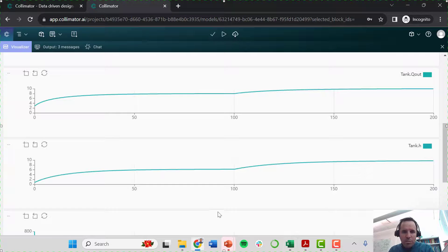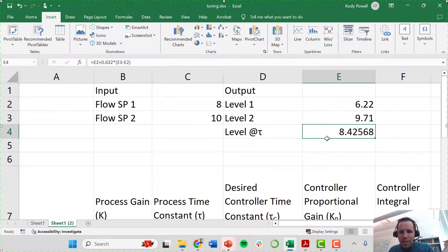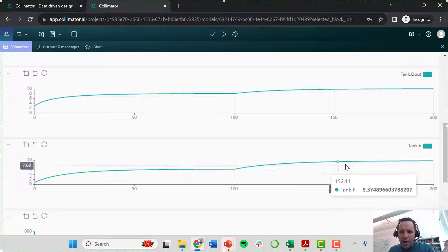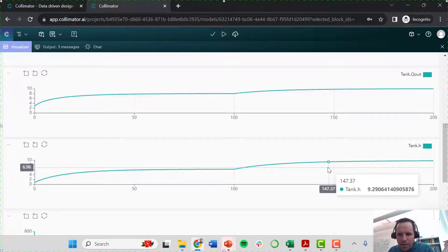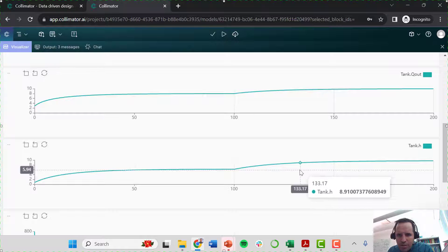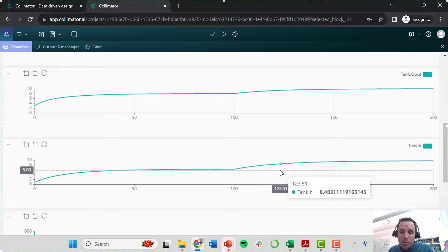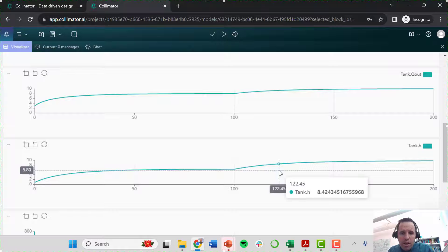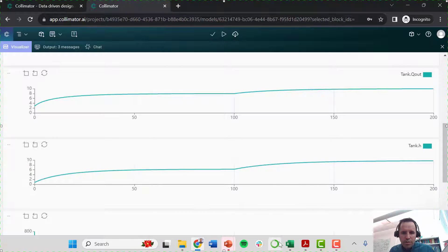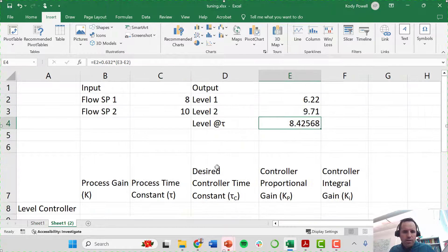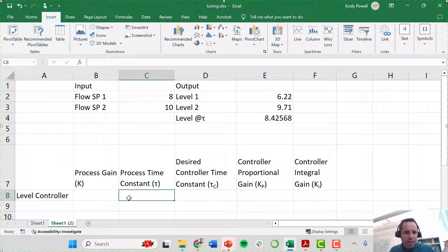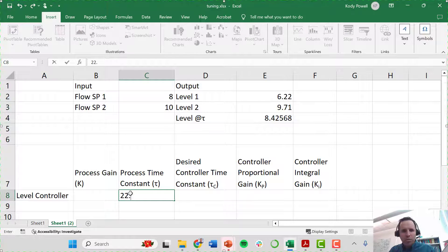Going back to the simulation model, the number we're looking for is 8.42. Hovering over the output variable plot, that level of 8.42 occurs at about 122 minutes. We made the step change at 100 minutes, so this gives us a time constant of about 22.5 minutes. So I go back to my spreadsheet and I have identified my process time constant to be about 22.5 minutes.